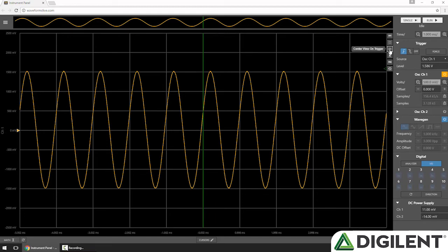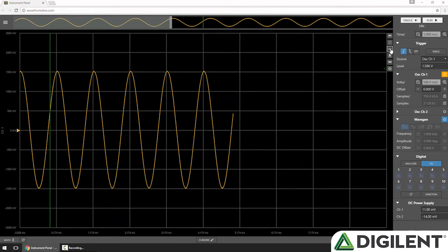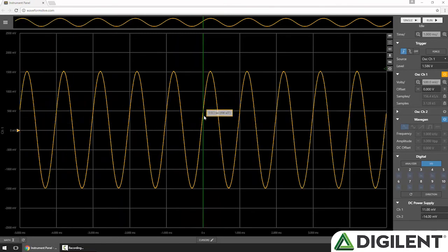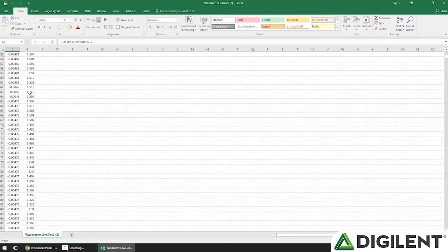Below that is the center on trigger button. If I pan off to one side and click that button, it'll bring the trigger back to the center of my screen. Next is the export button, which allows me to export as CSV or as a PNG. Below that is a button to display the device pinout, so you can easily tell which flywire connects to which instrument.